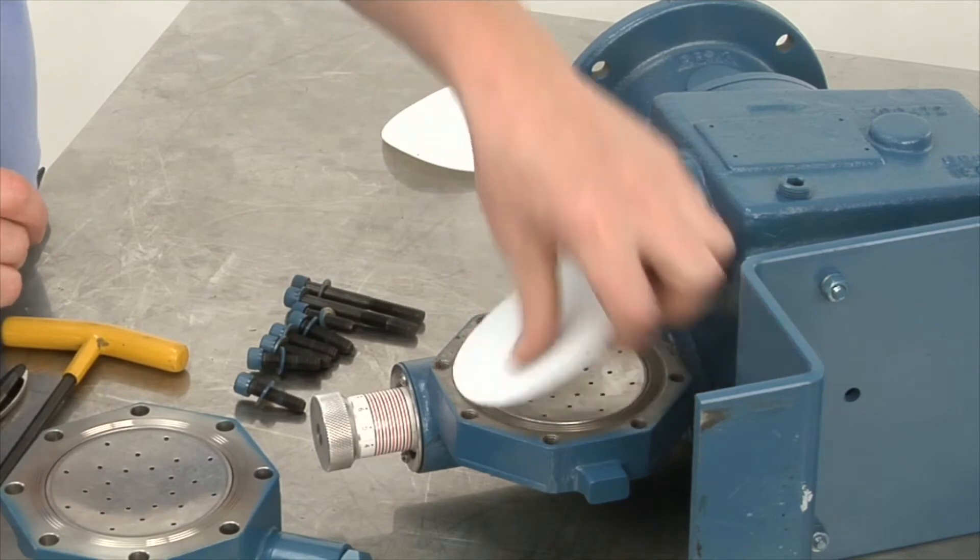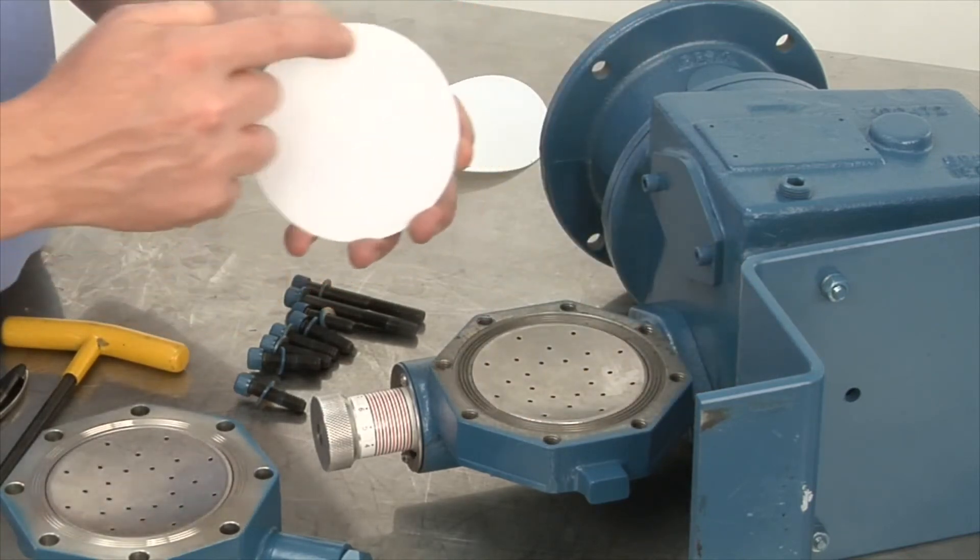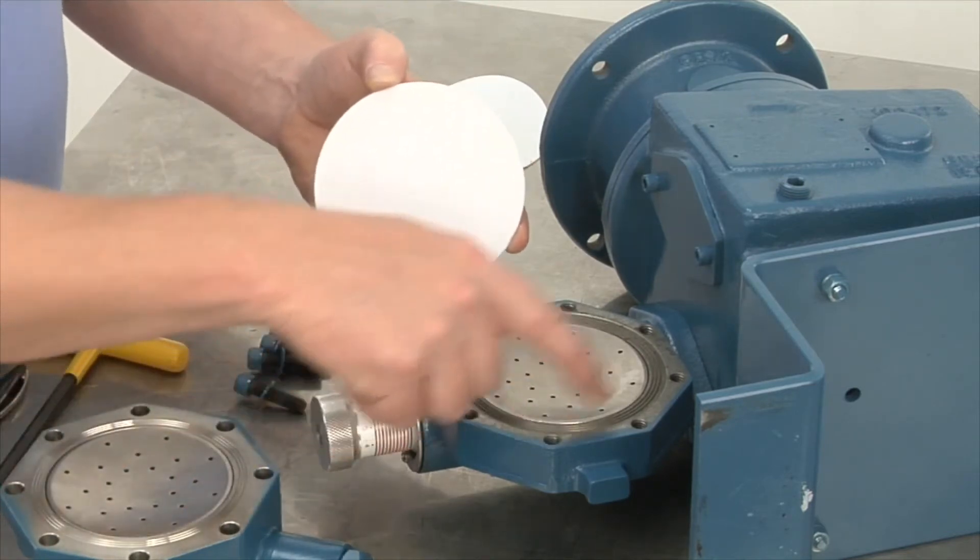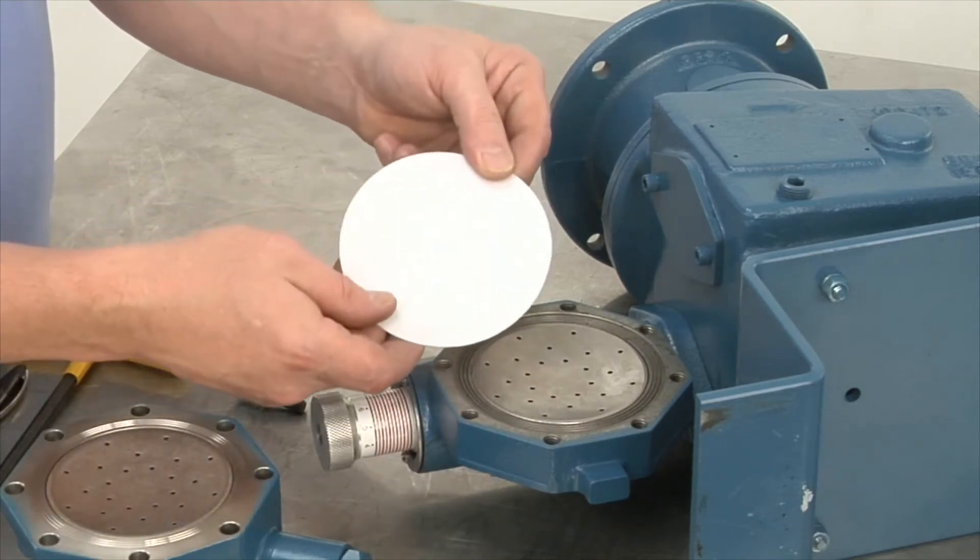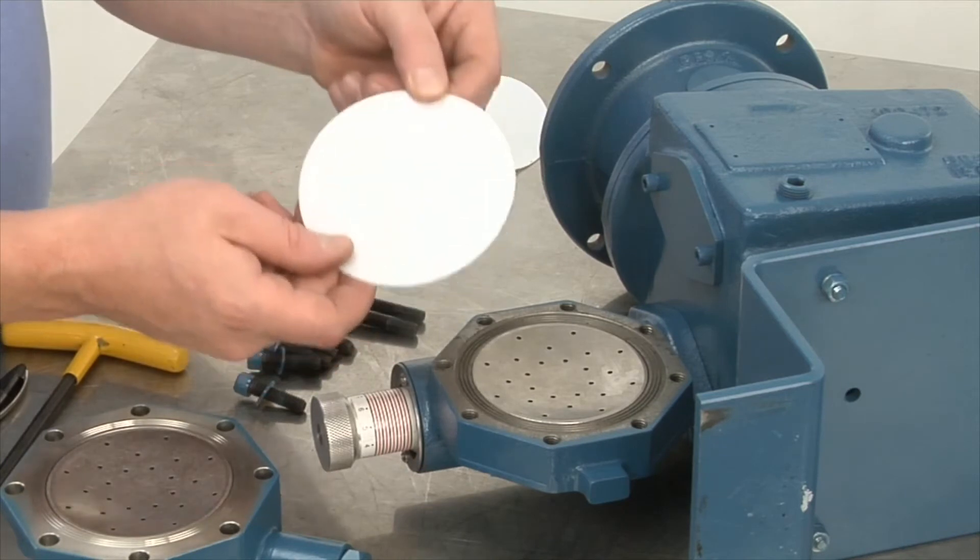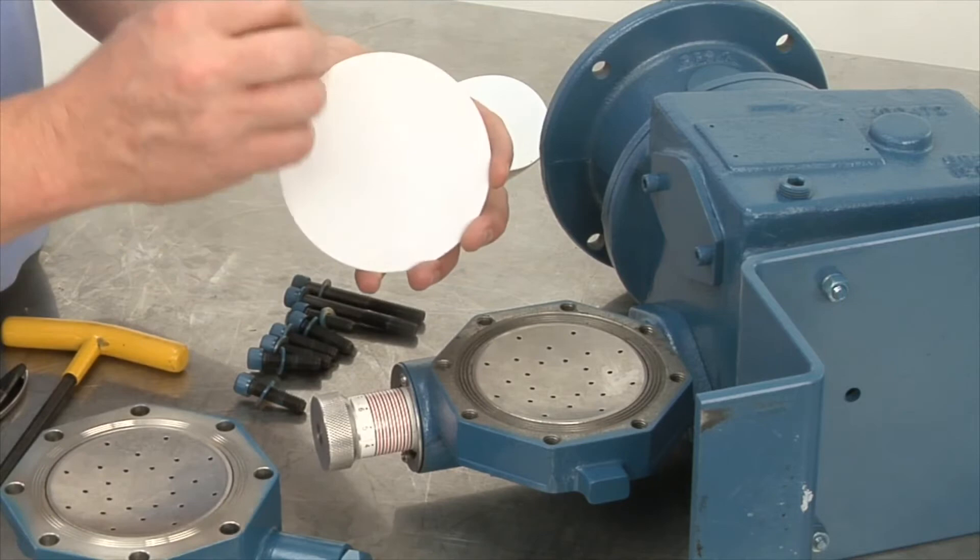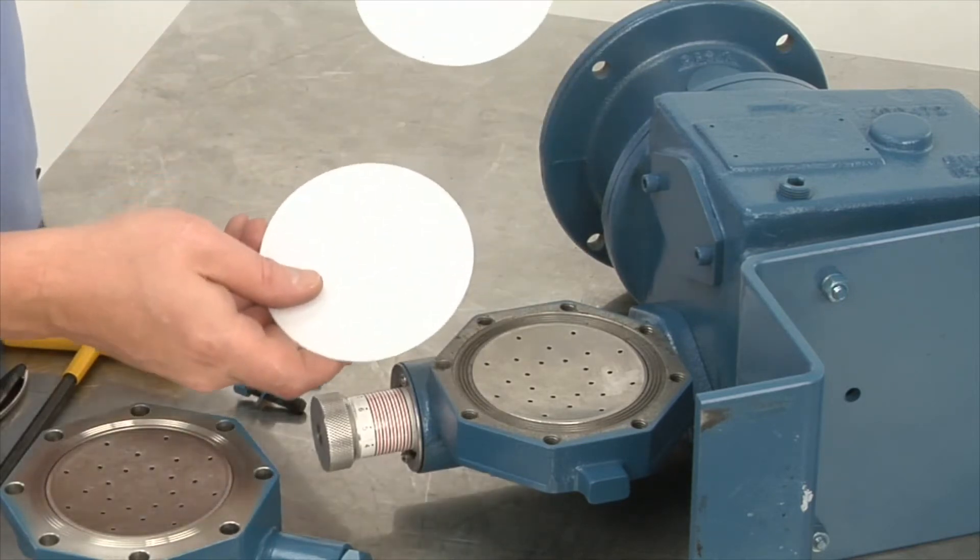Diaphragm is next. Diaphragm is made of Teflon. You'll see that it has an imprint on the outer surface that's from the head on both sides to make a seal from the oil and the liquid of the pump. We always recommend never to put a used diaphragm back into the pump because it's Teflon, which has no memory so it can't snap back and seal as properly as a new one will.